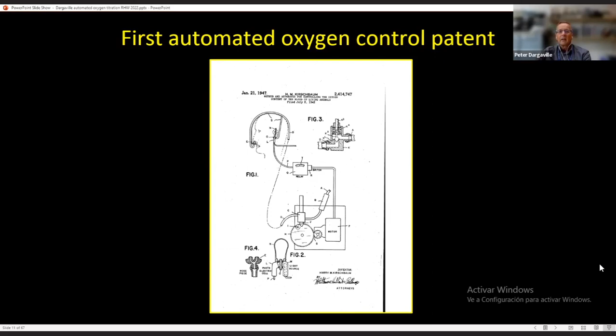Over the years, as we've come into this field, we've identified what we believe are the optimal features of an automated oxygen controller, and that it would involve an algorithm that is responsive, meaning able to make a measured and tempered response to SpO2 deviations in a system with a 30-second time lag.